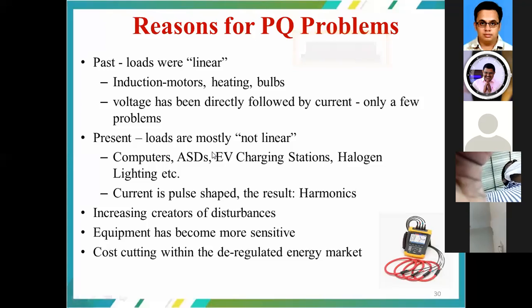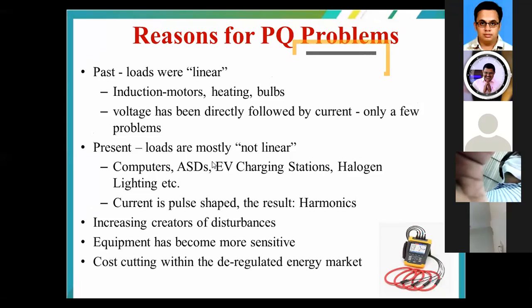The reason for the power quality problems is non-linear loads. In the earlier stages, 70% of the power consumed was by induction motors, and we used to call the induction motor the workhorse of the industries. We mainly utilized the power for heating and lighting purposes. In recent times, the penetration of non-linear loads such as computers, adjustable speed drives, EV charging stations, halogen light fixtures, or advanced luminaires are the issues wherein these non-linear loads play an important role in the generation of harmonics. And the current is pulse shaped, which results in the harmonics.